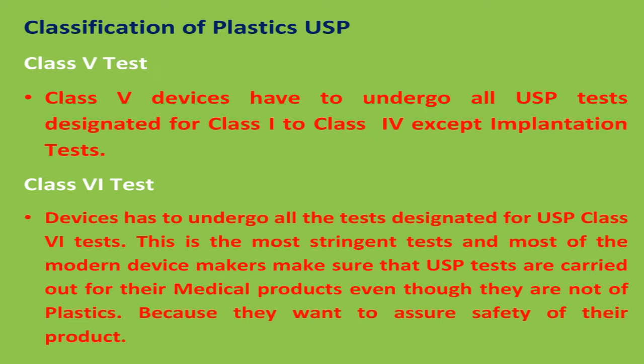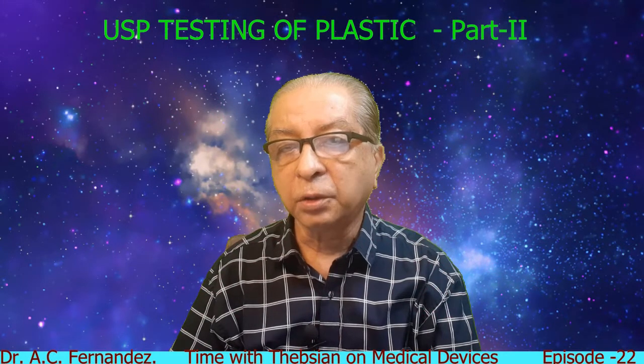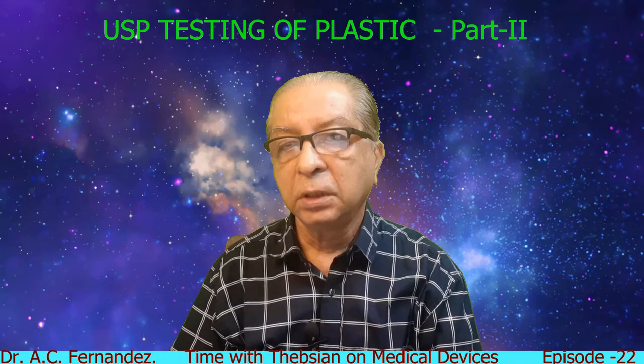Class 5, devices have to undergo all USP tests designated for class 1 to class 4 except the implantation test. Class 6, device has to undergo the tests designated for all USP classes. This is most stringent, and most of the modern device makers make sure that their devices, their materials for preparation and the end product undergo the USP Class 6 test. The reason is that they want to assure that their products are safe.